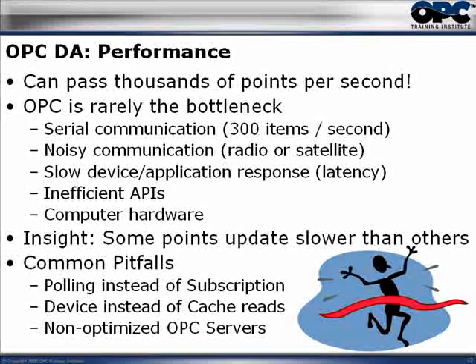Different vendors communicate with servers differently, so make sure you ask your OPC client vendor: do you poll for data or subscribe? Are you doing device reads or cache reads? How are you enabling the OPC server to optimize itself? Ask your OPC server vendor: how do you optimize communication with the PLC? Do you get priority for writes or reads? Can you do multiple reads at the same time? Different OPC products have far, far different performance characteristics.